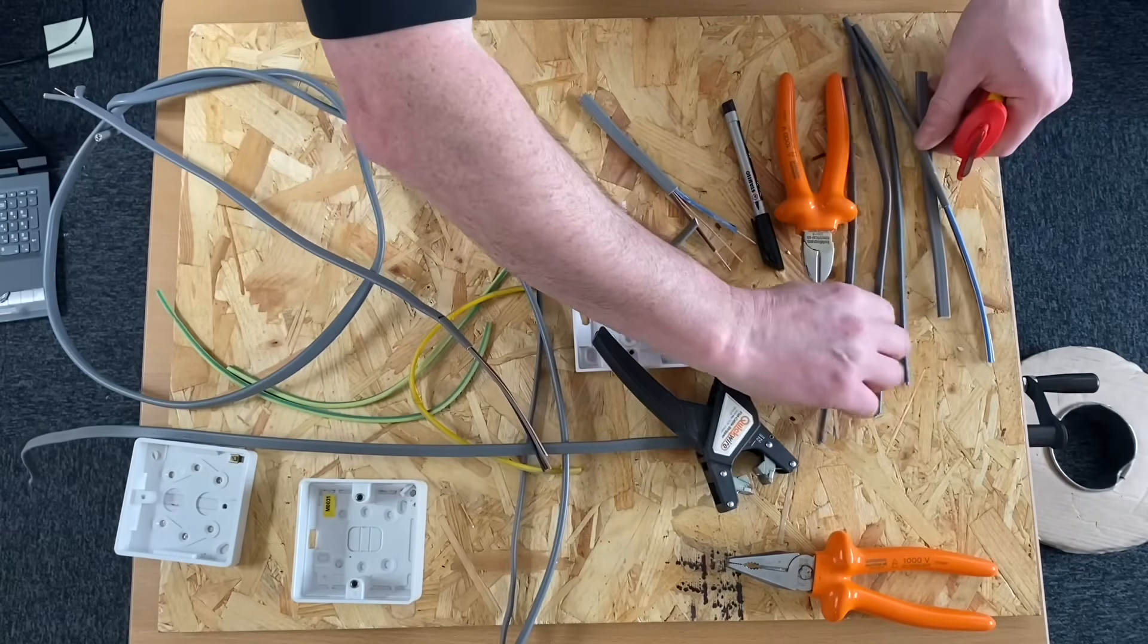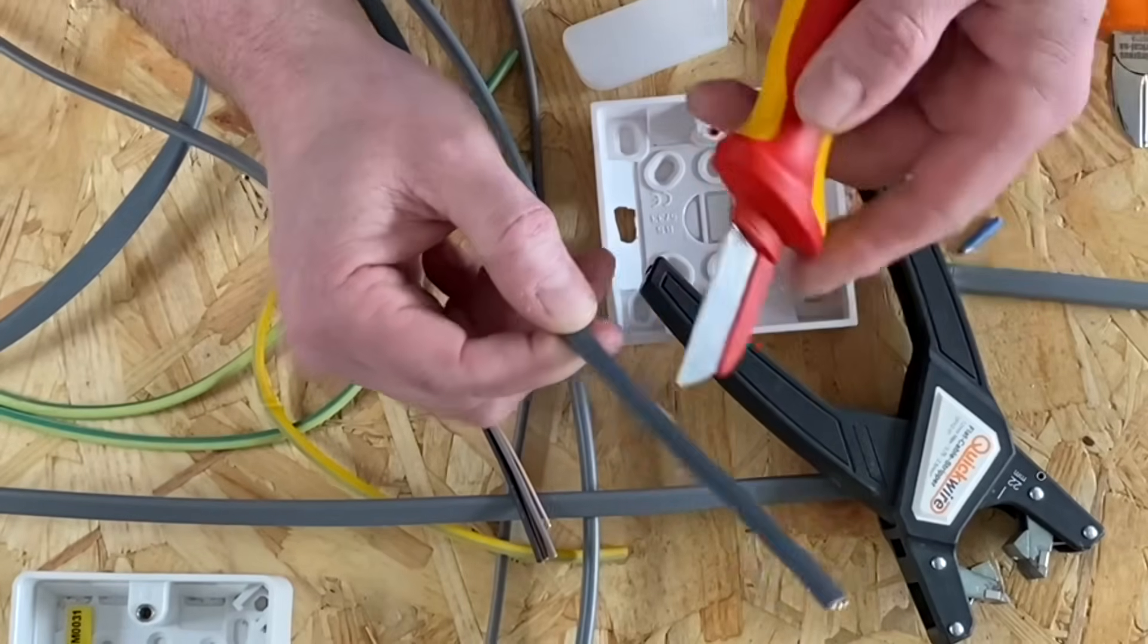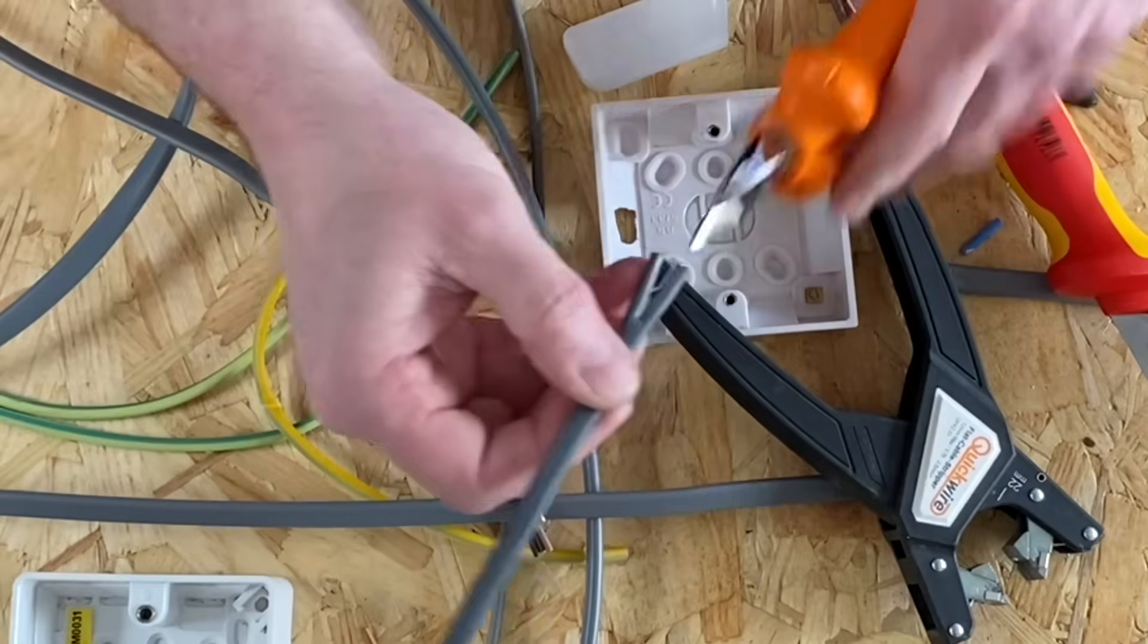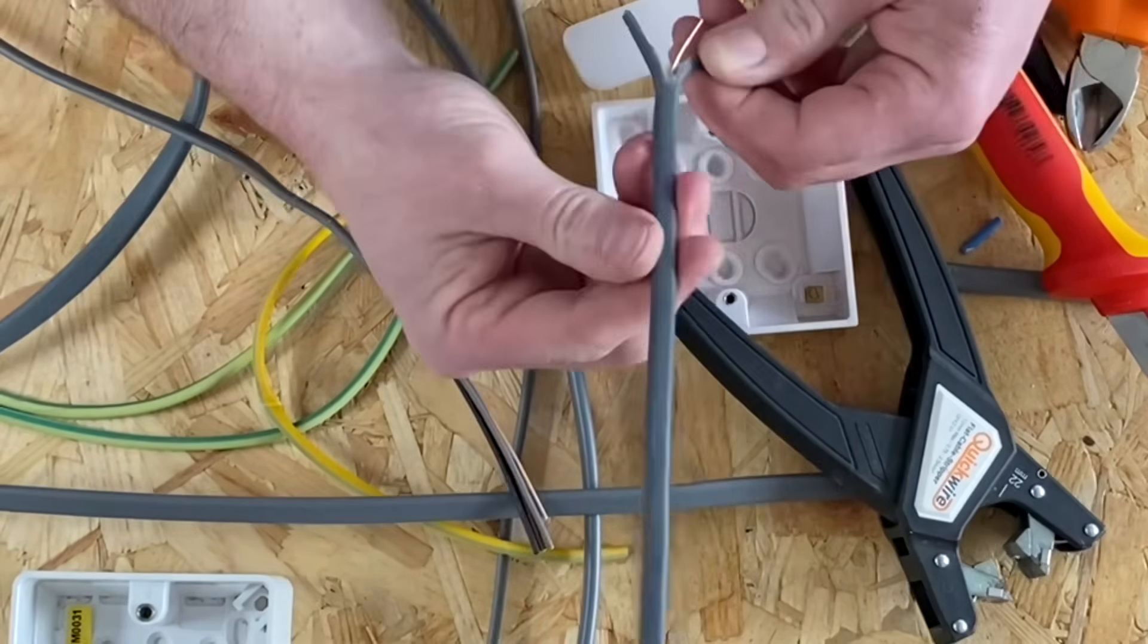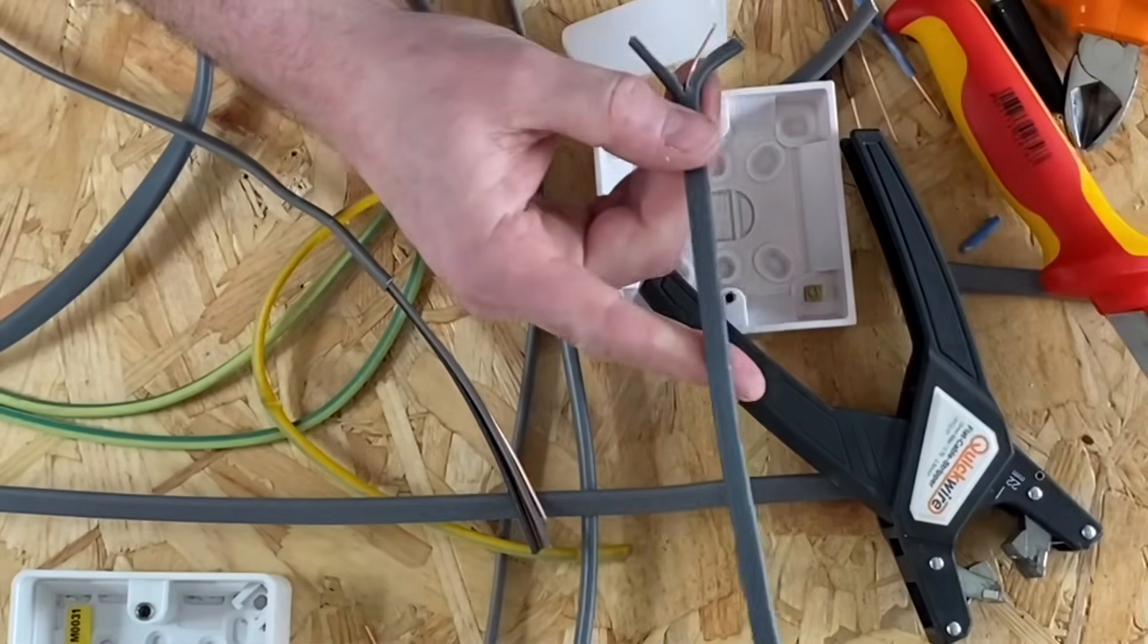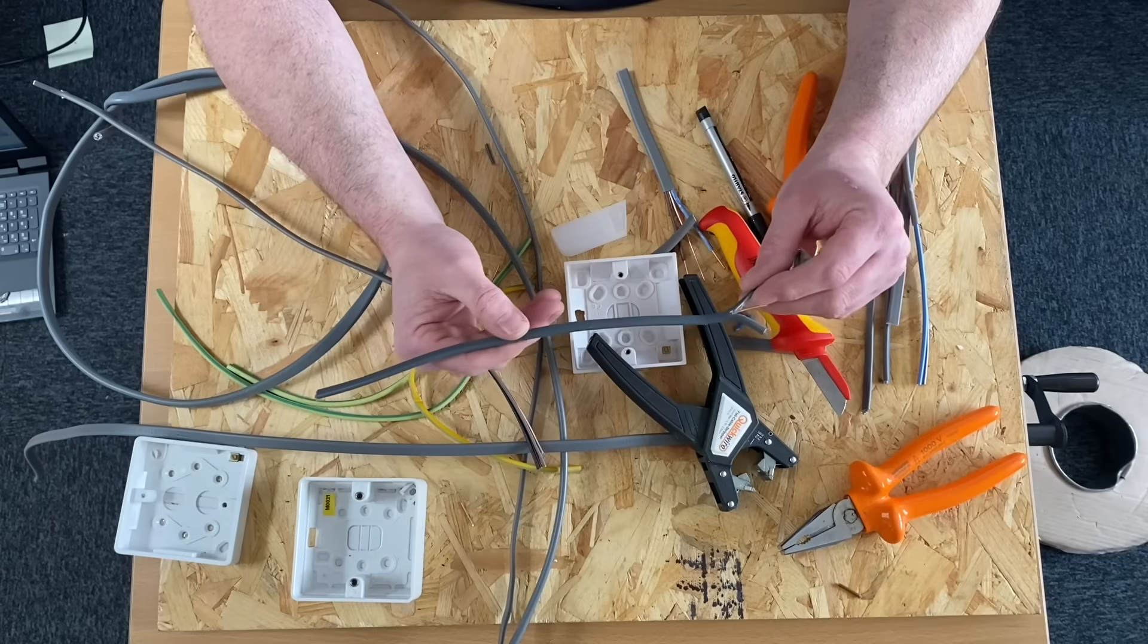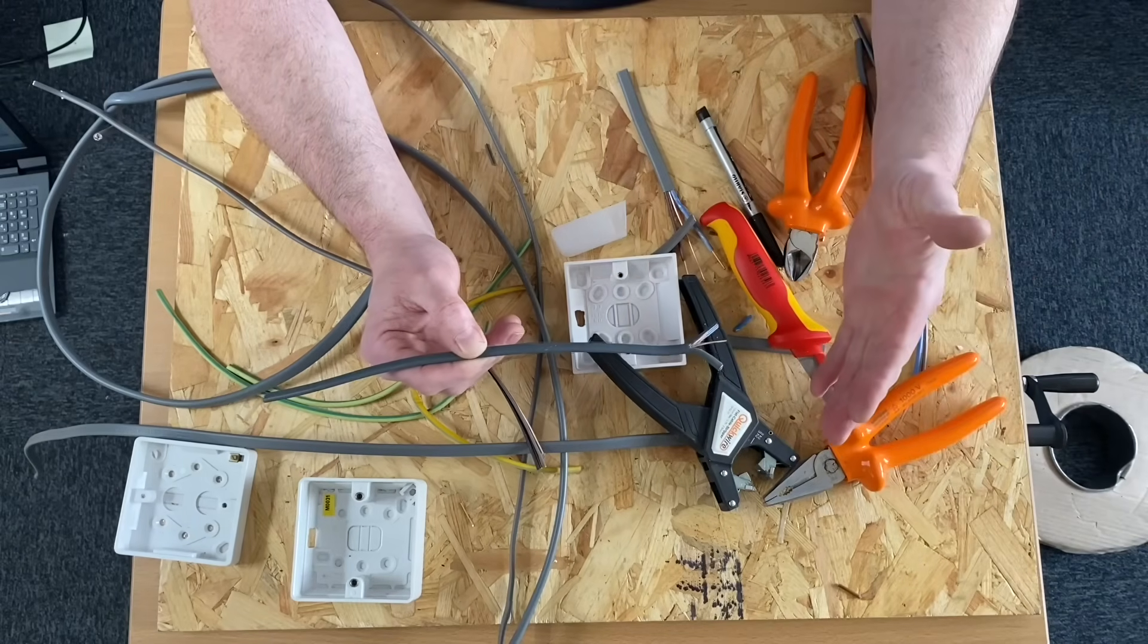Let's strip a piece of cable using my knife just to remind you of the technique. So gently score not saw around the actual mechanical protection itself. Then I get my learners just to snip down the middle of the cable, like so, and we leave our CPC in the middle. And what you're thinking now is, why don't you teach people just to grab hold of the CPC, Gary, and pull it down to the scored area you've got down here. The reason being is we use lengths often less than half a meter long very early on. And what I've had before is learners actually not pull up on these, but actually pull away.